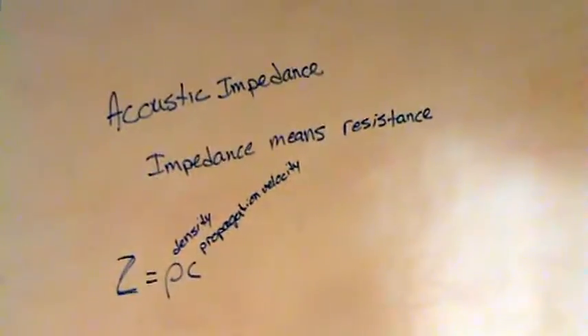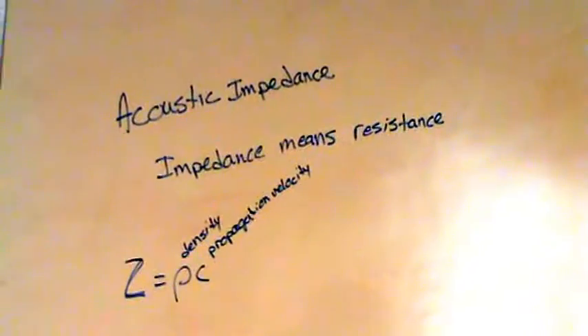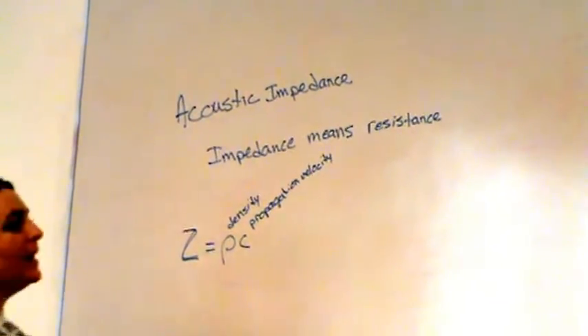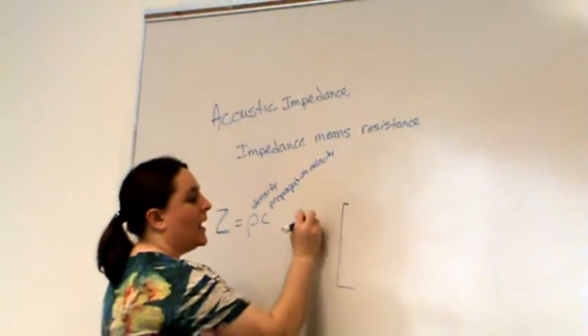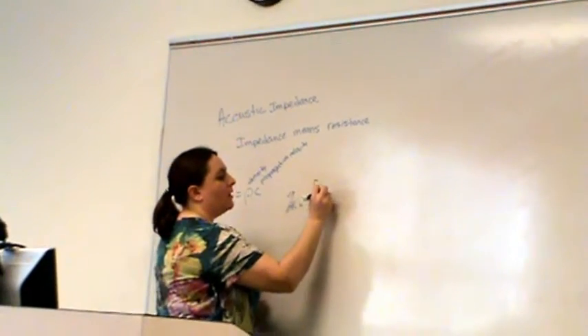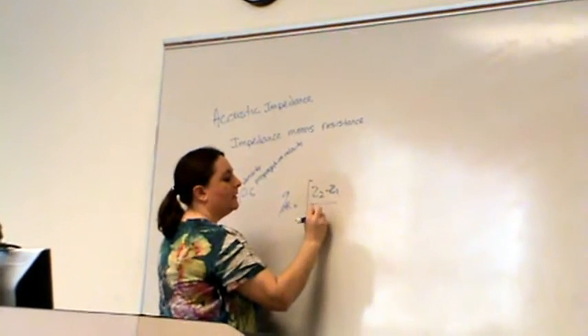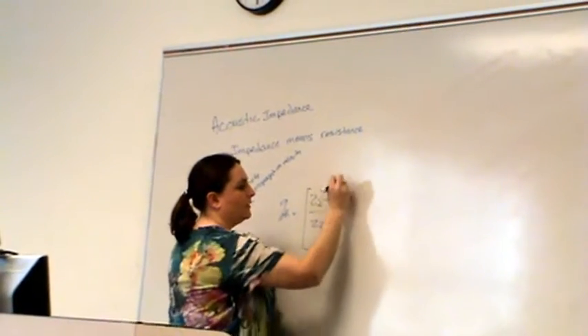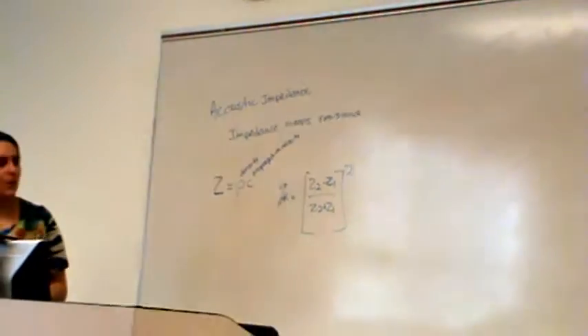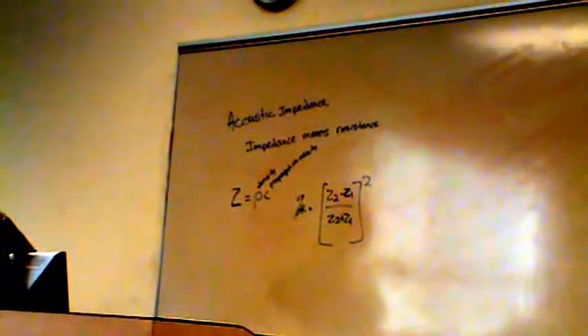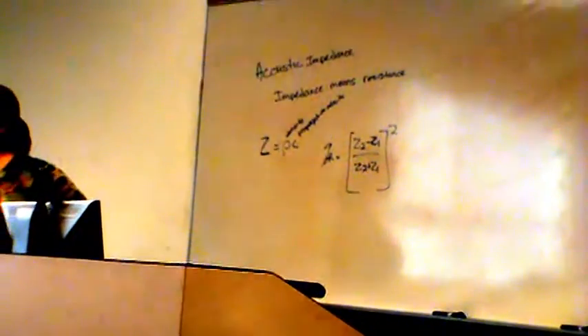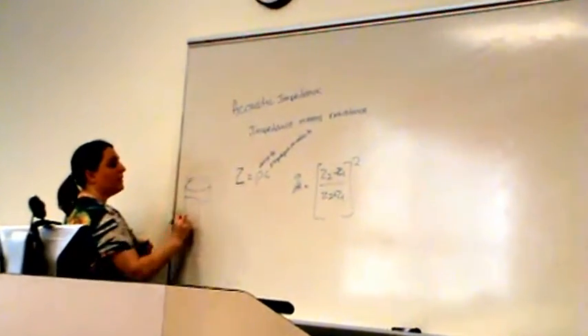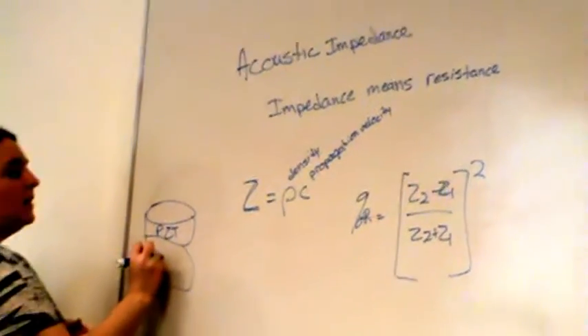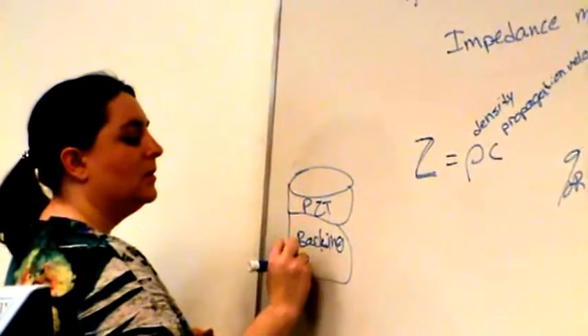And remember, in order to get a signal to happen, we have to have that acoustic impedance mismatch thing. And we have this big, long equation that told us what percent of the beam would be reflected at different interfaces. So remember, this idea of acoustic impedance not only applies with the body itself, but this also applies to the transducer. Remember, we have the transducer construction, and we talked about the PZT layer, and we have the backing material, or the damping layer, whatever.